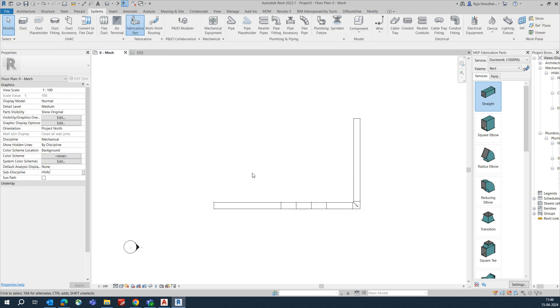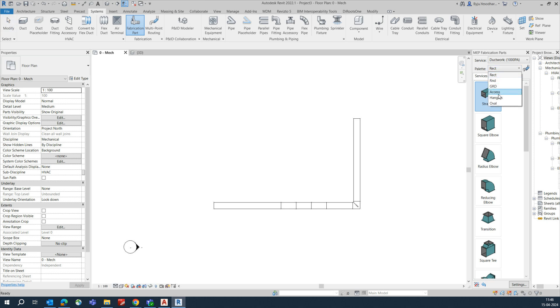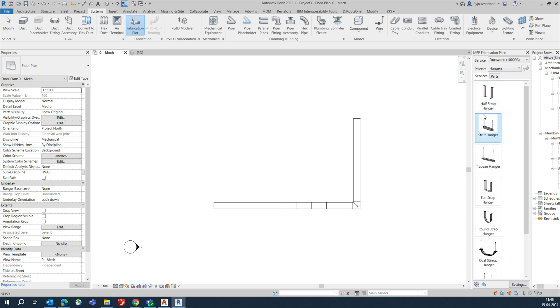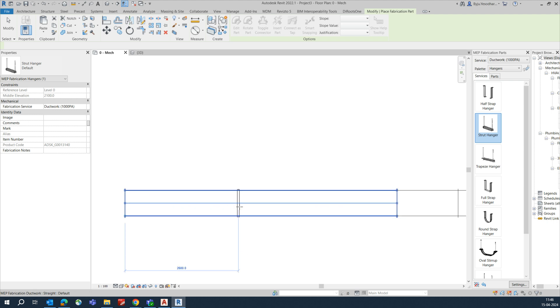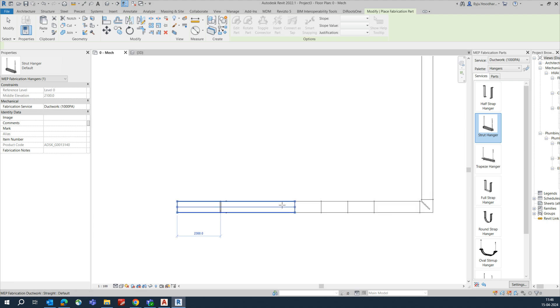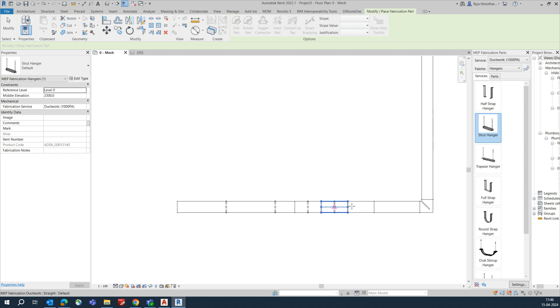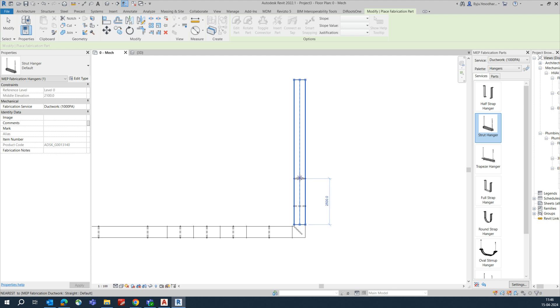Next, add fabrication parts for supports. Go to the fabrication parts panel, drop down to Hangers, and select one. You'll get many hanger types to choose from. I'm placing supports at each end and the middle of the duct — the hanger automatically adjusts to the size of the duct.